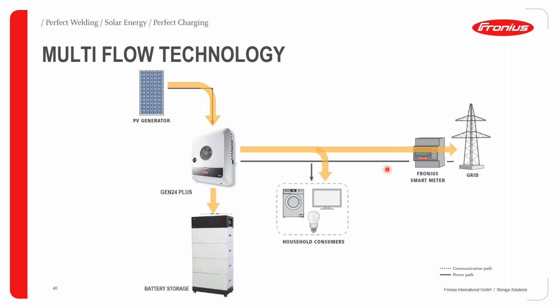So in this kind of scenario in Africa, if you have the battery already incorporated, especially during the day, and the loads are consuming a lot of power, and you still have excess that can be seen mostly in SolarWeb, at this moment you can decide to also retrofit the Ohmpilot to generate hot water using the excess PV energy. Another aspect of the multi-flow technology could be that during the day the solar panels are not generating as much energy as they should, maybe due to overcast conditions, or dust cover, or something happening with the strings of the array. Therefore, the energy stored in the batteries is able to supplement what the loads are consuming at that point. So you also have the possibility of different flow directions from the PV and the battery simultaneously to feed the loads. Also, as mentioned in the previous slide, you can recharge your batteries using grid power, depending on the kind of configuration you want in your system.